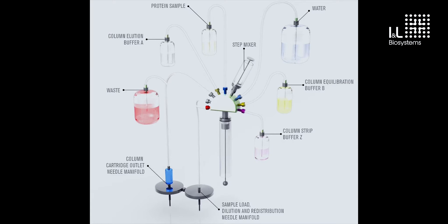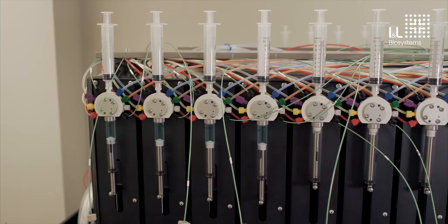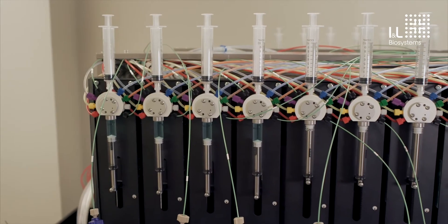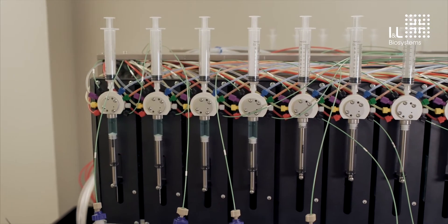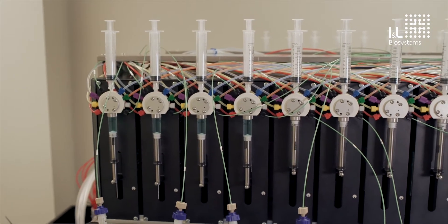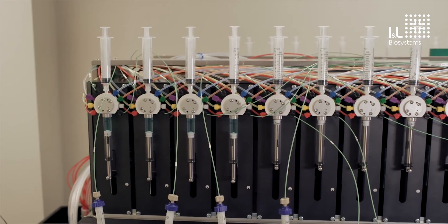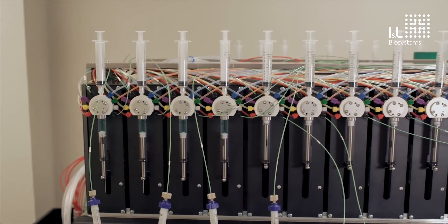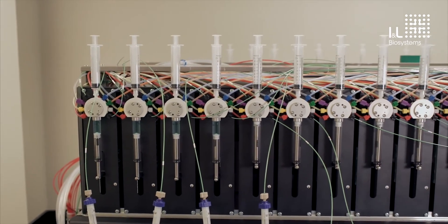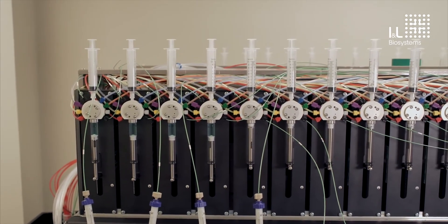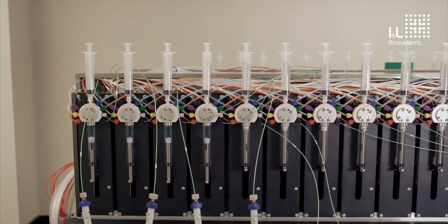In this setup, we have a number of different buffers connected. We have a waste position, we have a step mixer that enables the automated mixing of multiple buffers on the fly, and we have one line enabled to aspire samples from the fraction collection deck. Again, every tubing represented in this schematic is replicated on each of the 24 pumps, providing maximum flexibility for you to perform the experiment you desire to do.